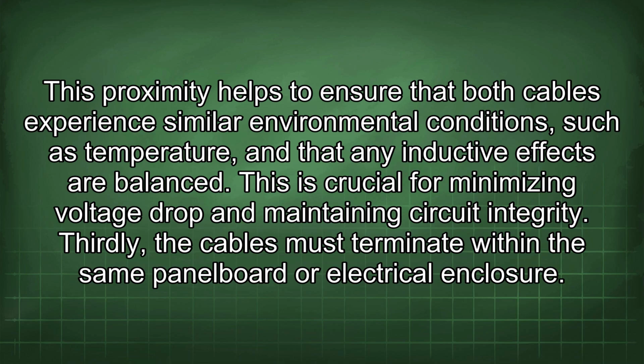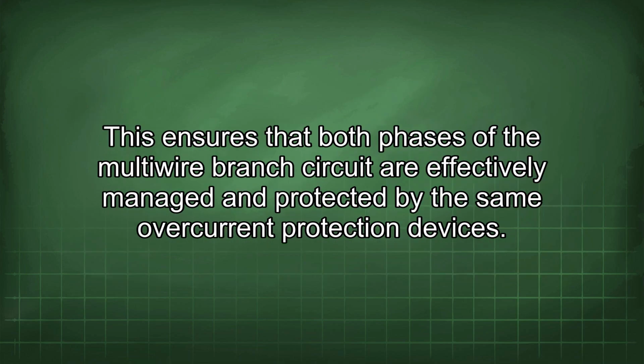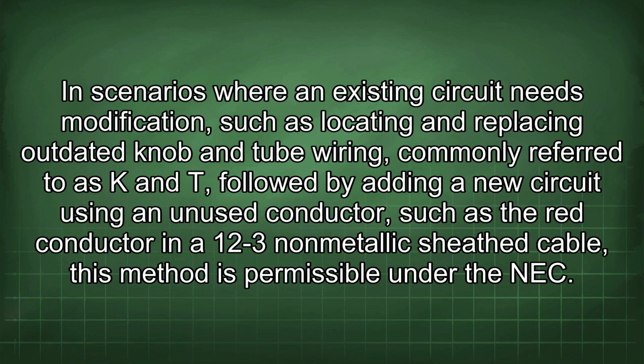Thirdly, the cables must terminate within the same panel board or electrical enclosure. This ensures that both phases of the multi-wire branch circuit are effectively managed and protected by the same overcurrent protection devices. In scenarios where an existing circuit needs modification, such as locating and replacing outdated knob and tube wiring, commonly referred to as K&T, followed by adding a new circuit using an unused conductor, such as the red conductor in a 12-3 non-metallic sheath cable, this method is permissible under the NEC.